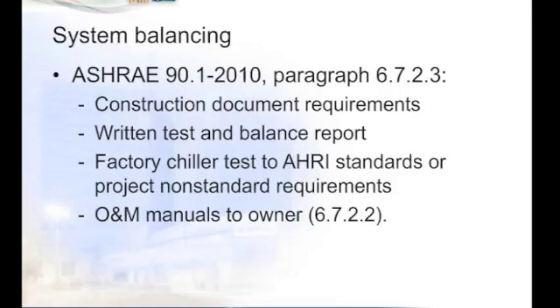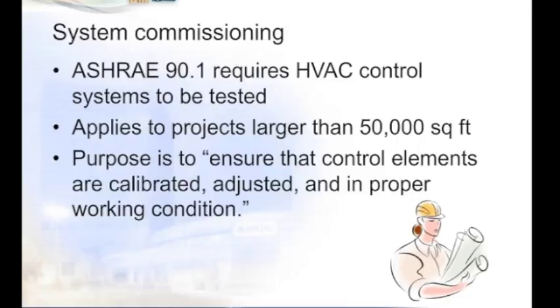And Jason, you can talk about the efficiency requirements, I'm sorry, the commissioning requirements. That's the one. All right, today we thought it'd be important to bring up that there are commissioning requirements in 90.1 and just remind everybody of that. Now, the requirements in 90.1 are less than detailed, but they do provide some guidance that allows you to bring this in as a requirement on your projects. So 90.1 requires that all control systems must be tested. Now, this is a very short statement, and that was a little bit of paraphrasing from 90.1, but it is short, and it's open to interpretation. There are many ways to accomplish that testing, in quotes.